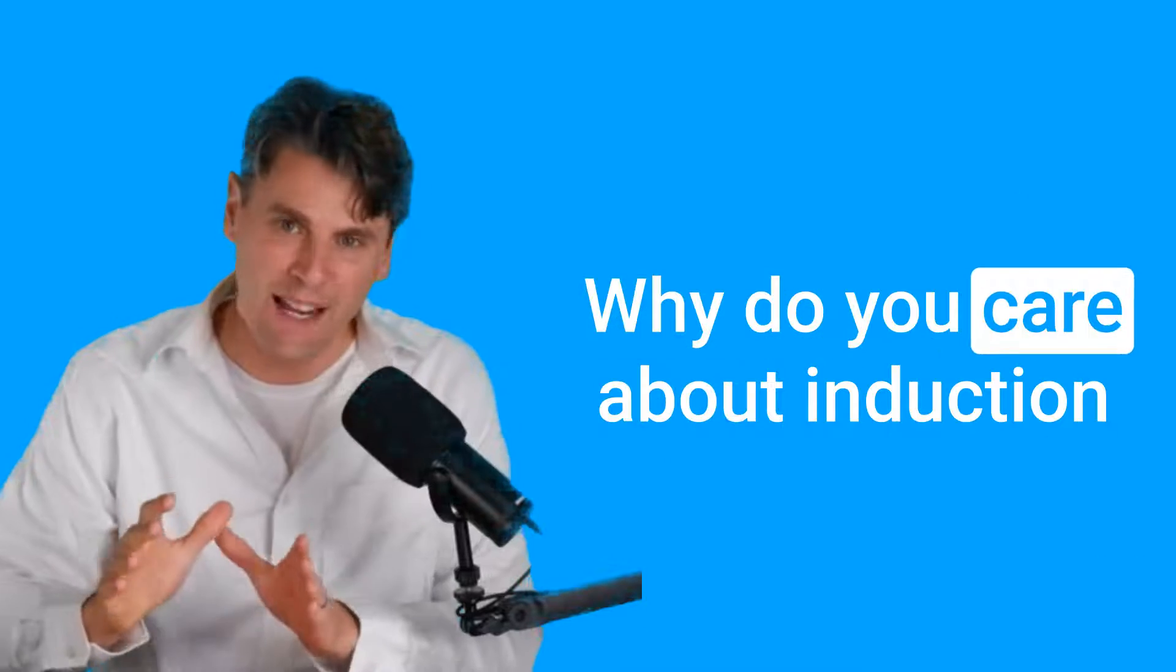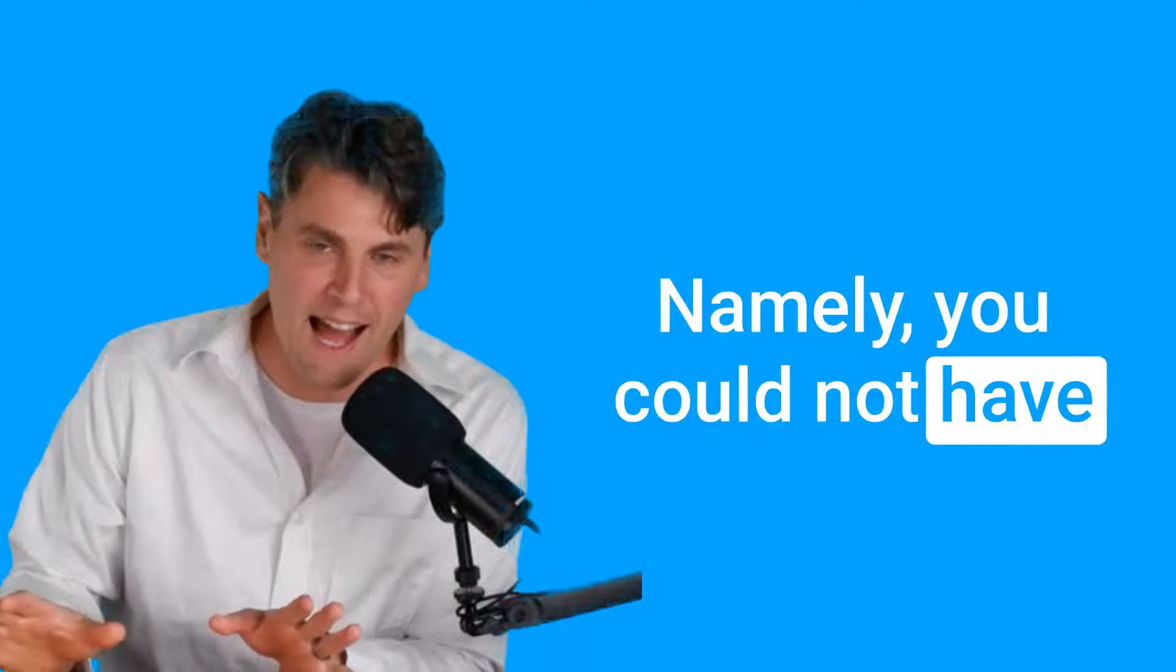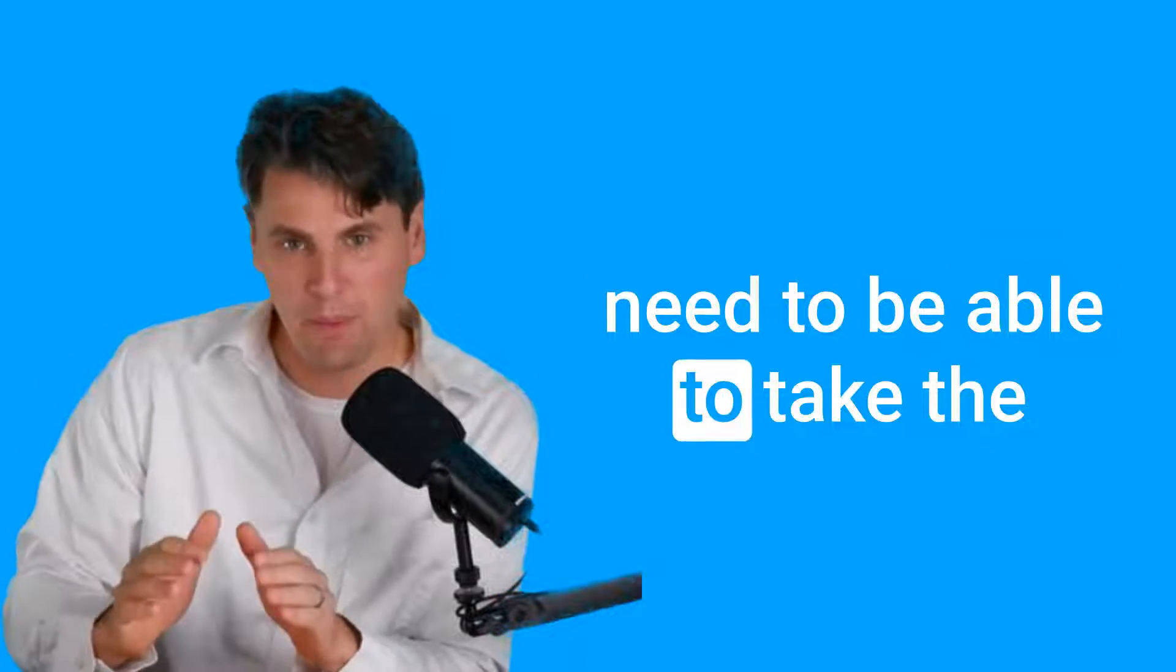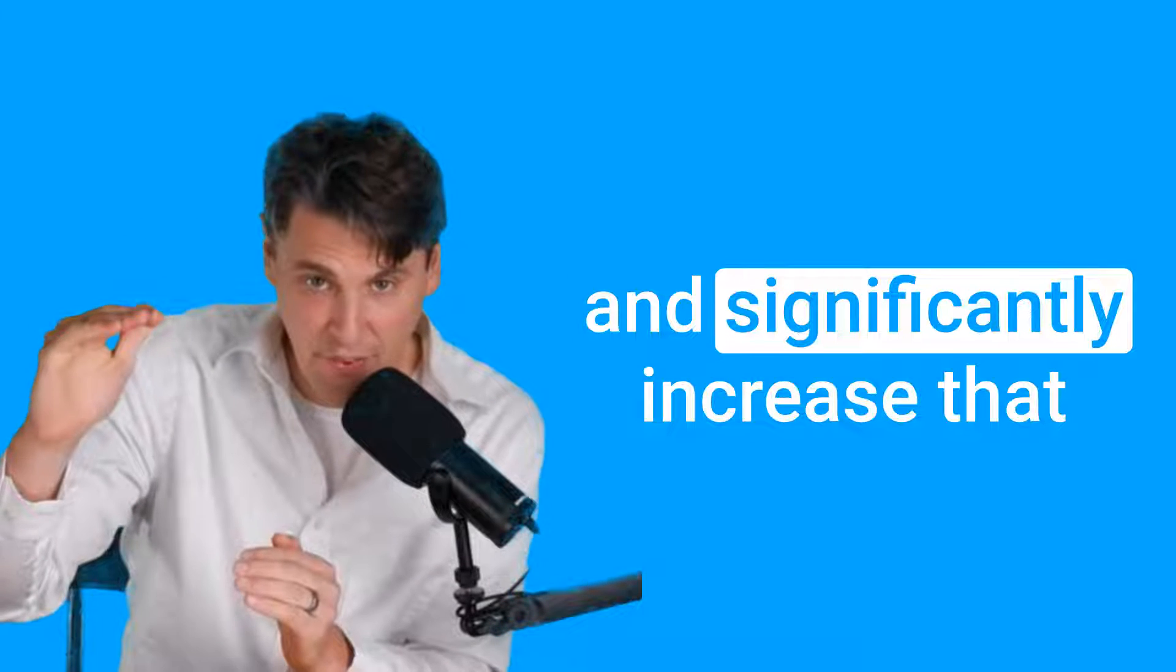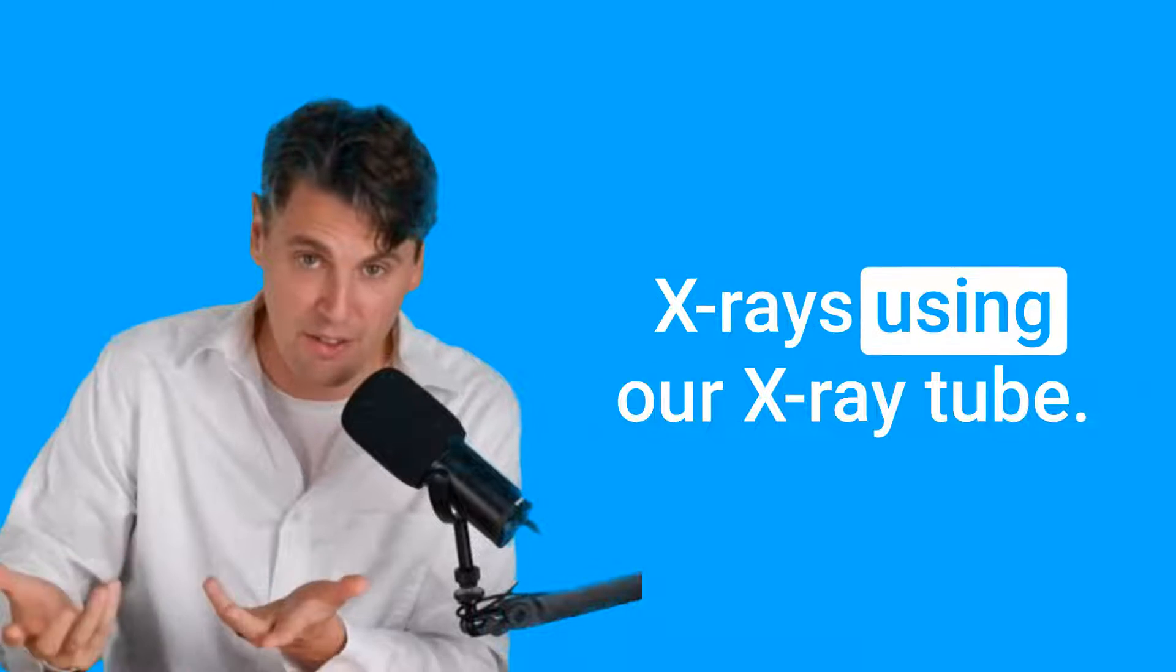Coming up now, why do you care about induction and transformers? Namely, you could not have an x-ray circuit without transformers. You need to be able to take the voltages that we get at the wall and significantly increase that voltage in order to produce x-rays using our x-ray tube.